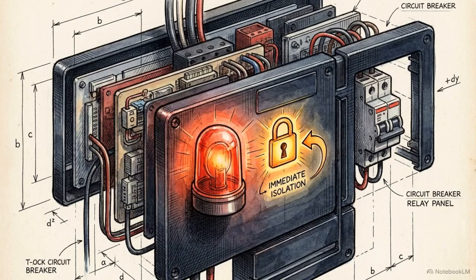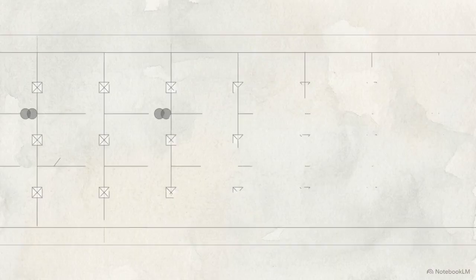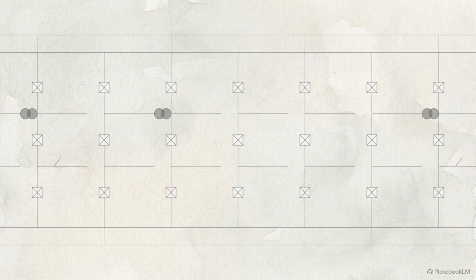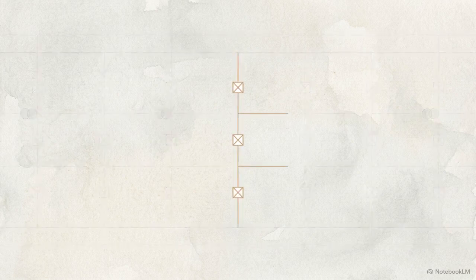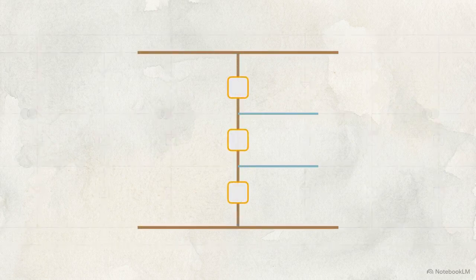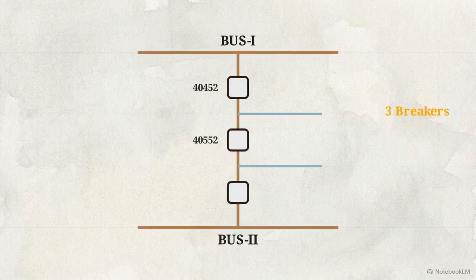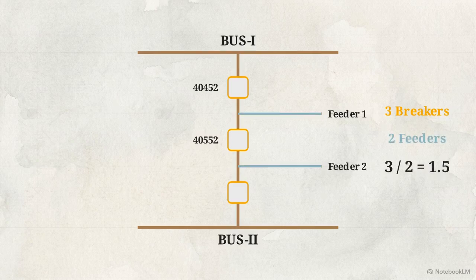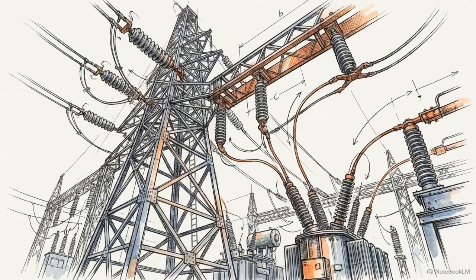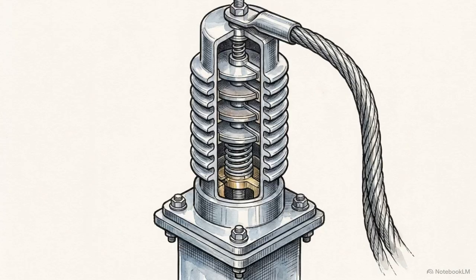Returning to the EHT Substation schematic, the chaos resolves into structure. If we isolate a single bay, we see a perfect match to our theoretical 1.5 breaker model: 2 main buses, 3 central breakers, and 2 outbound feeders. Moving out toward the transmission lines, we find the specialized protective boundaries, including the specific capacitive voltage transformers measuring the voltage and surge arresters ready to bleed off external voltage spikes.